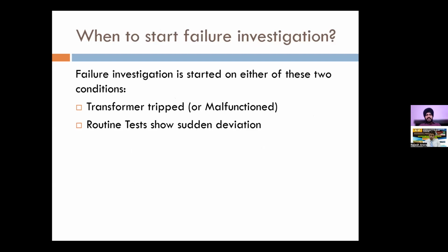Now, when to start the failure investigation? It can get triggered by one of these two conditions. If a transformer has tripped, at that point of time failure investigation will start. Or, if the transformer was in service but you have taken it under shutdown and the tests show a sudden deviation. It does not mean that the transformer was in service; it may have been out of service and you now intend to take it in service, or it continues to be in service and you have observed some deviation in the DGA parameters. So any routine test which shows a sudden deviation, or a transformer tripping, can be a trigger point for the failure investigation.